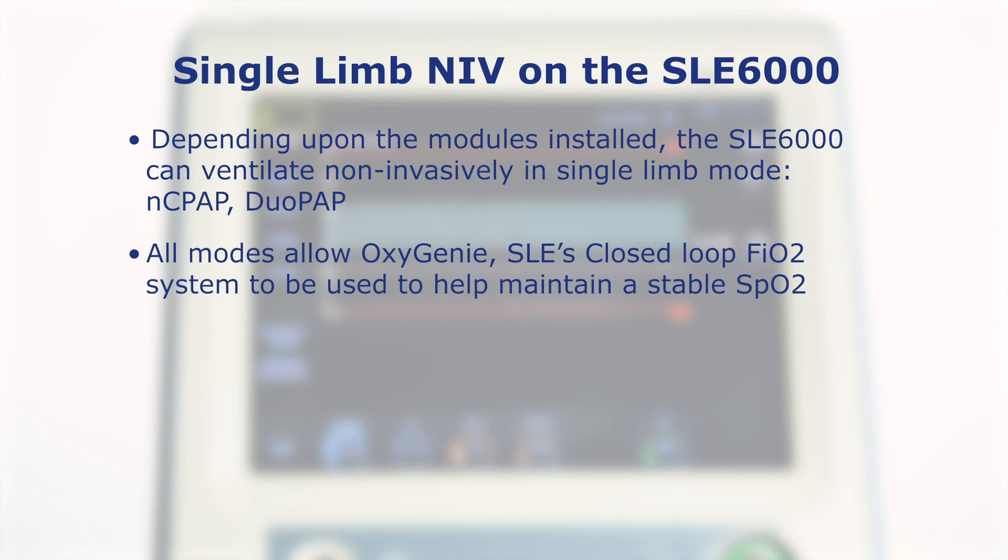Depending upon the modules installed, the SLE6000 can ventilate non-invasively in single limb mode: NCPAP and DUO-PAP. All modes allow OxyGenie, SLE's closed-loop FiO2 system, to be used to help maintain a stable SpO2. All modes are designed to work with SLE's multi-purpose circuit.